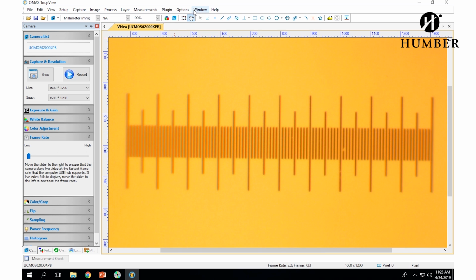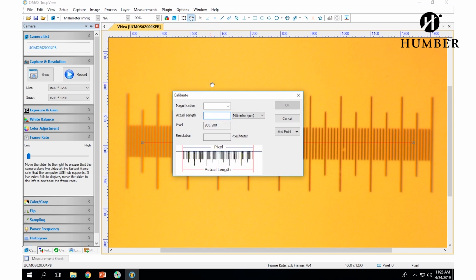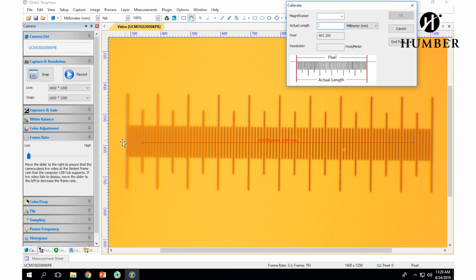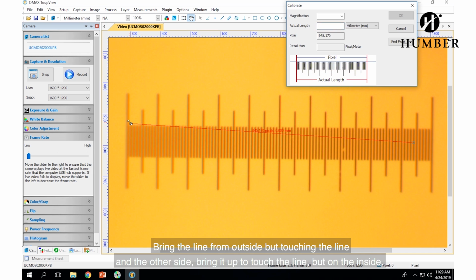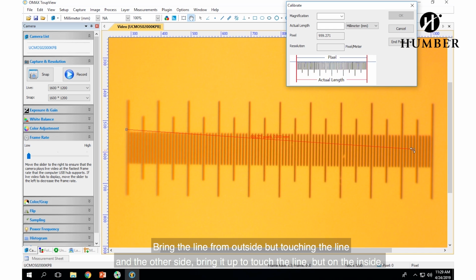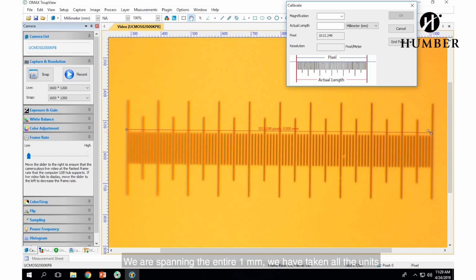You want to then go on to the option, select Windows, sorry, select Options, and select Calibrate. So move this window which you have seen to the top right hand corner. The moment you have selected calibration, you see a red line which has come up. Bring that line such that it is on the outside but touching the initial line, and the other one you want to bring such that it is touching the inside of that line. We are spanning the entire 1 millimeter. So we have taken all the units from the outside to the inside, touching.